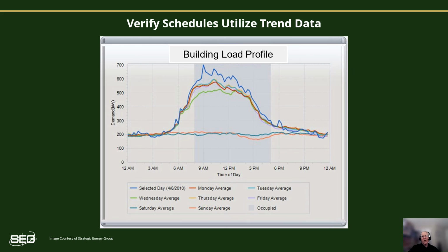Note there's a 200 kilowatt base load where the consumption never goes below this level. Most all buildings will have a base load that they simply don't drop below at any time. But in this example, 200 kilowatts after hours, there may be some opportunities here for savings.